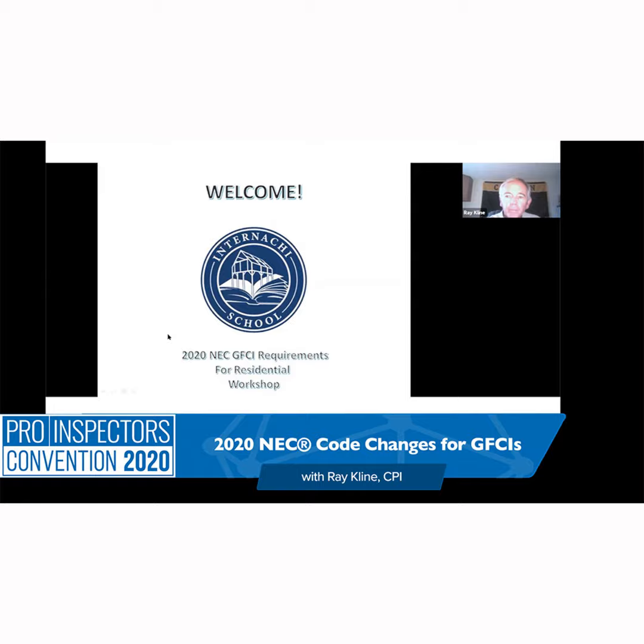And I probably would mark that one pretty high on my list of issues, because that has to be accessible. That pump's got to be accessible for maintenance. That GFCI has to be accessible for maintenance as well, or just for safety. Sometimes you can find they put in what's called a dead front GFCI, and it fits in an electrical box just like this. It has the test buttons at the top and the bottom, but it's not a receptacle. It's just trip and reset.